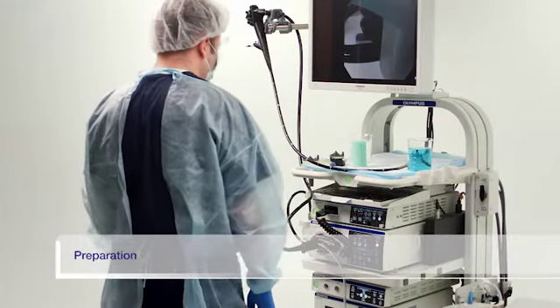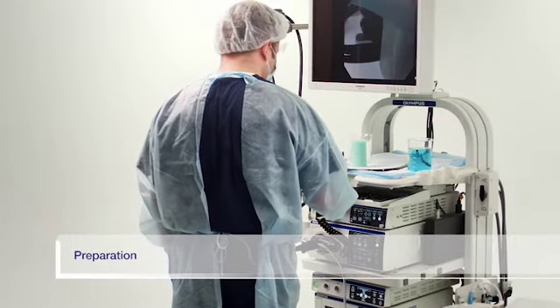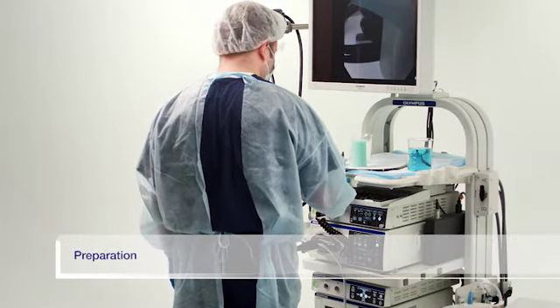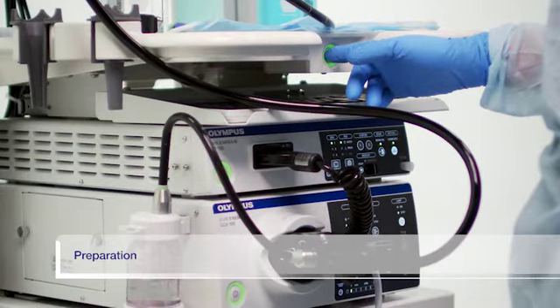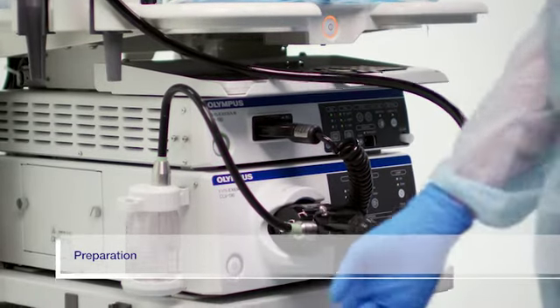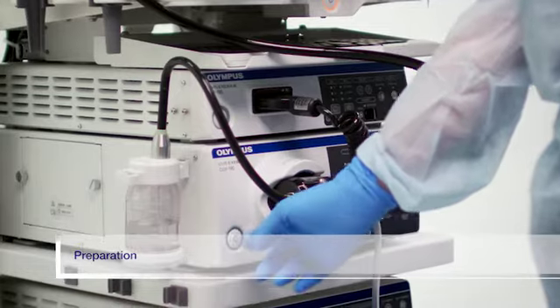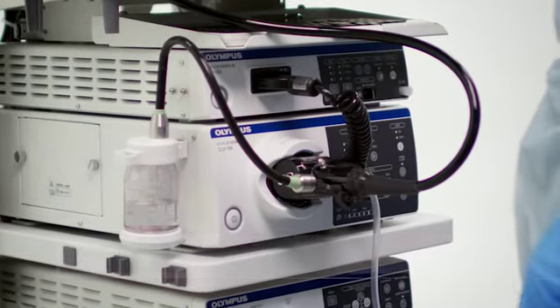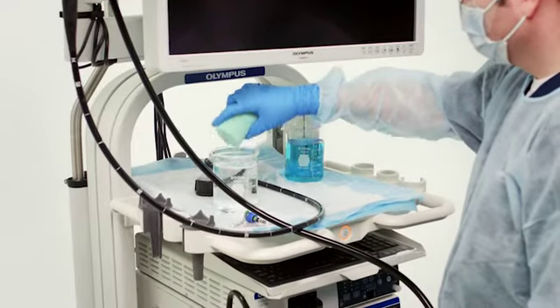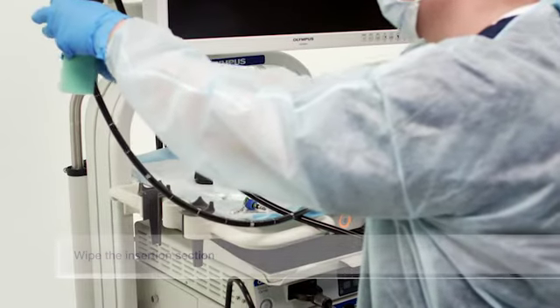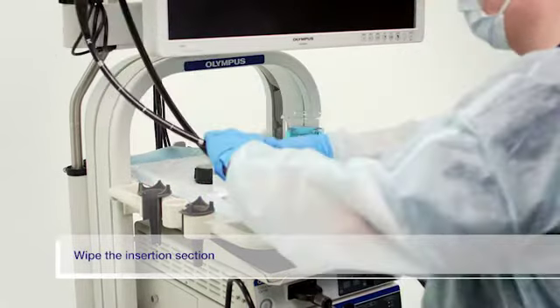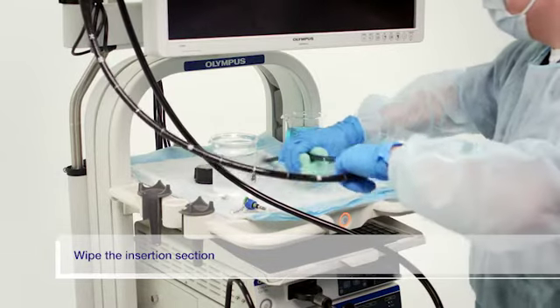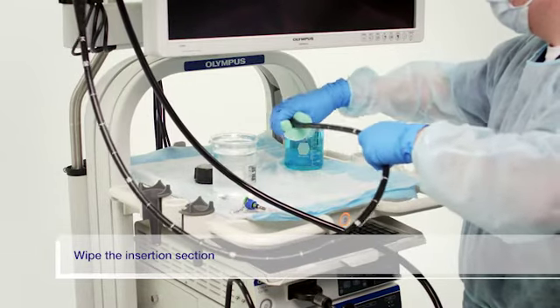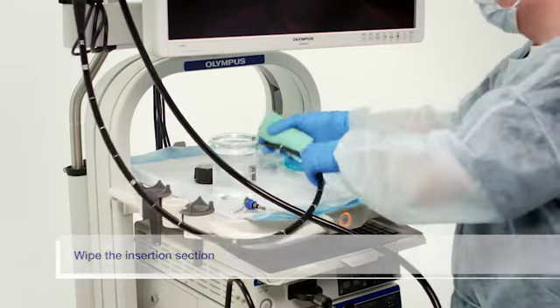Immediately following the patient procedure, with the endoscope still connected to the equipment used in the patient procedure, turn the video system center and light source off. Prepare a clean 500 milliliter container of water. Dip a clean, lint-free cloth or sponge in the clean water and wipe the entire insertion section of the endoscope. Wipe from the boot at the control section toward the distal end.